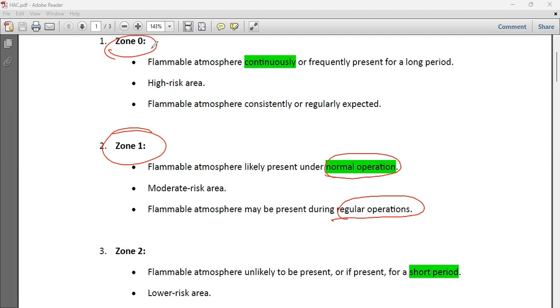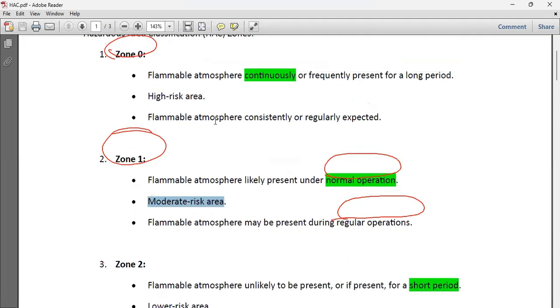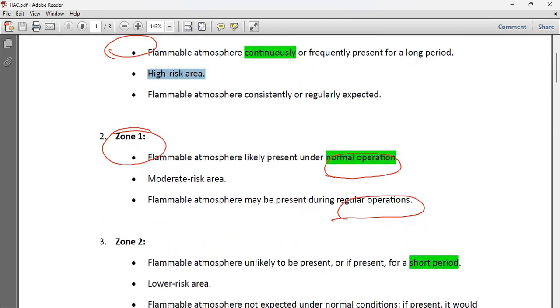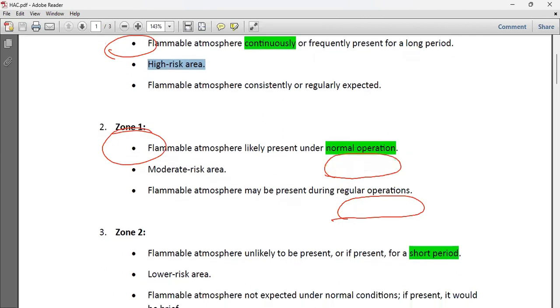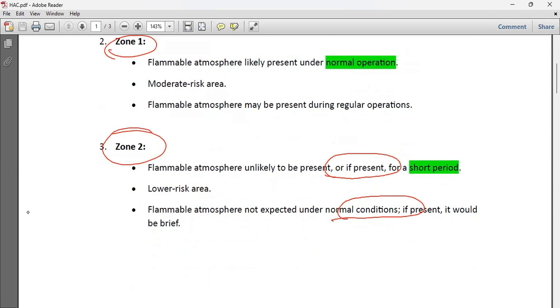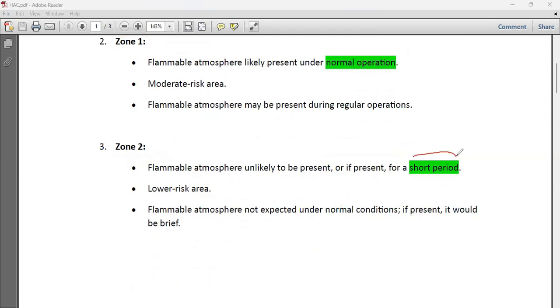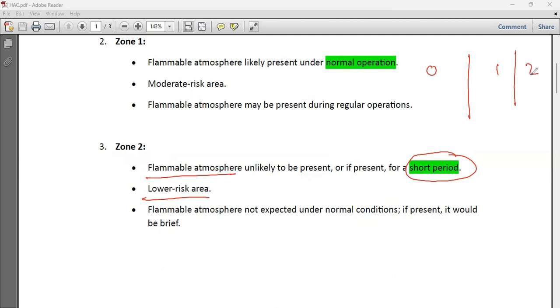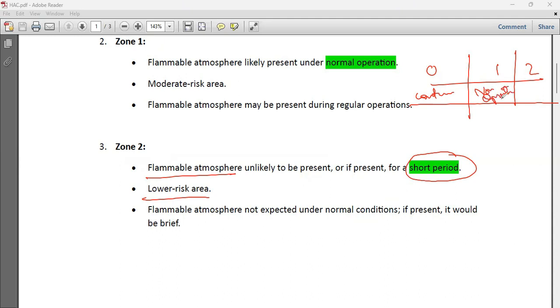Zone 1 means the flammable atmosphere is present only during normal operation — for example, when you are opening or closing a valve, or operating a hydrocarbon compressor. Zone 1 is moderate risk. Zone 2 means the flammable atmosphere is present only for a short period of time — it is the lowest risk among the three zones.